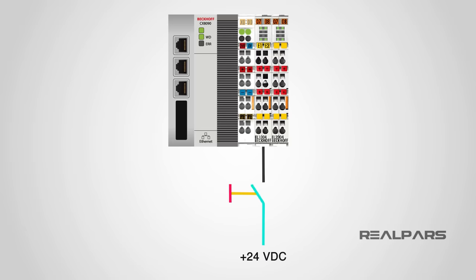Now, let's say that unaware to you, a wire that is connected to the lower part of the contact has been disconnected and you are not aware of it. Now, what happens when there is an emergency? Well, when there is an emergency, you press the emergency stop switch, but the switch will not work. Why? Because the wire has been disconnected and you are not aware of it.